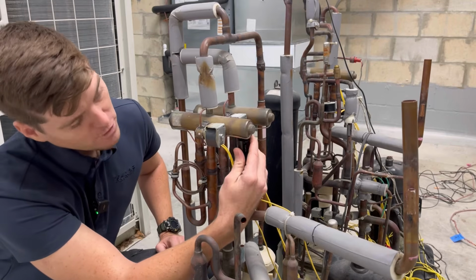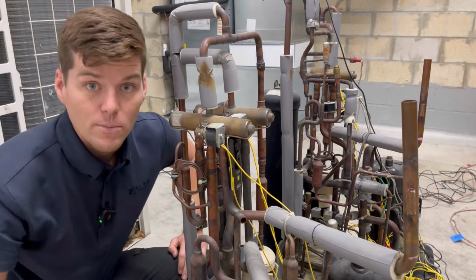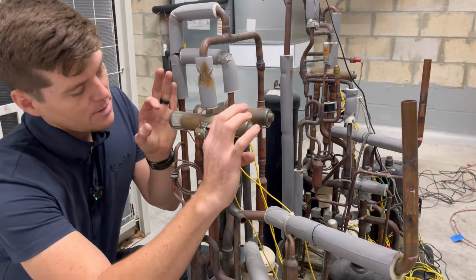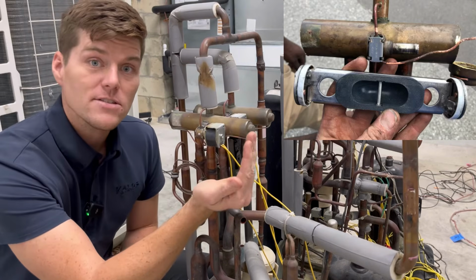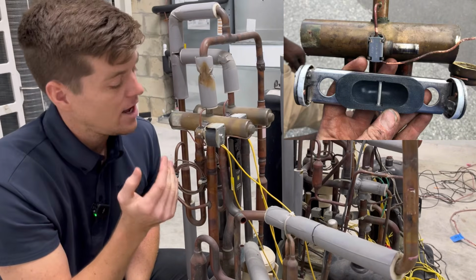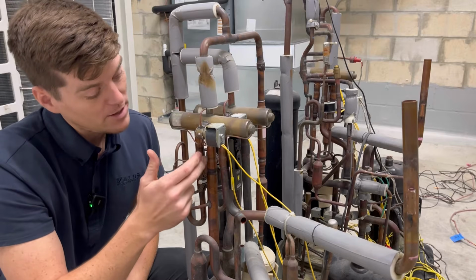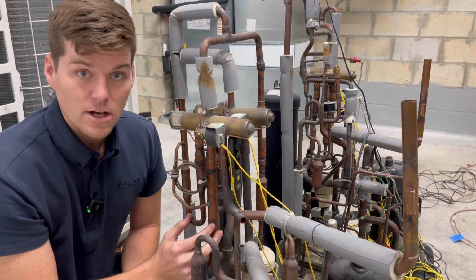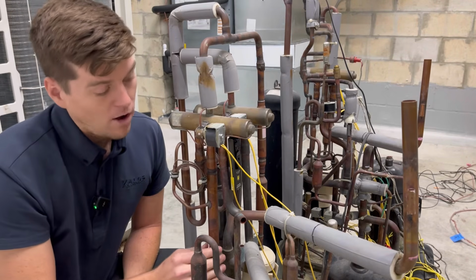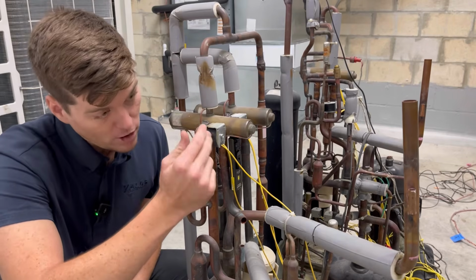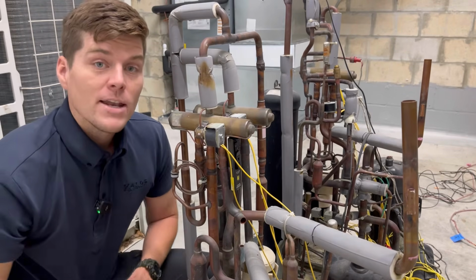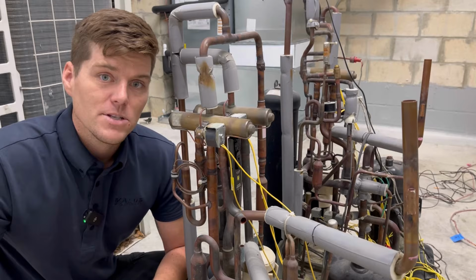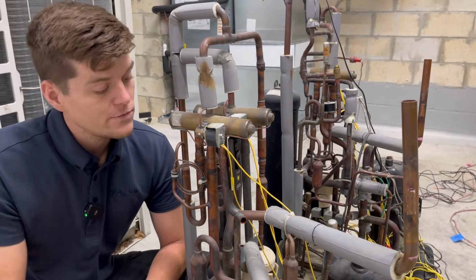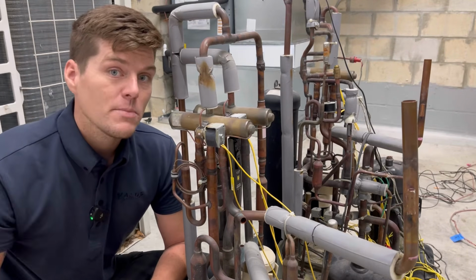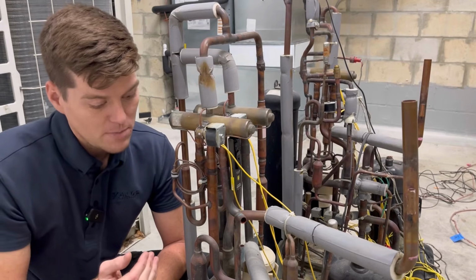However, if I move further back on the chamber, you'll find that, boom, it grabs the actual assembly that's inside of here, which tells me that this assembly has shifted to the left-hand side, which means it's all the way to the left, connecting my suction line back over to my suction line. It's dead-headed right here on itself, which means the hot gases should be flowing this way, up and over. Now, based upon the mode that my system is in, whether it's in cooling or heating, it'll tell me if this four-way valve is on or off. The service manual will tell you which direction that's supposed to be.